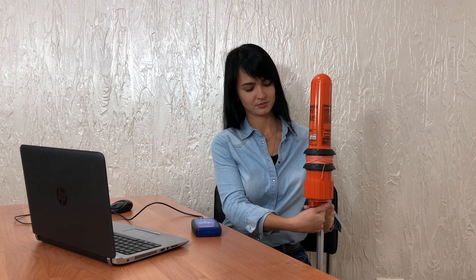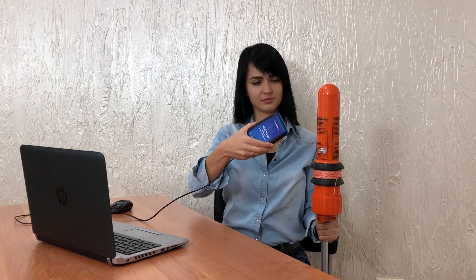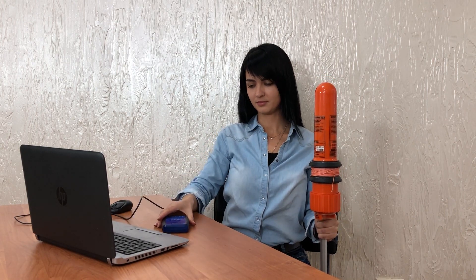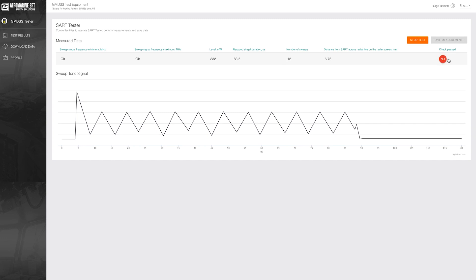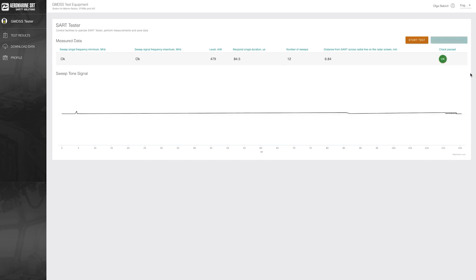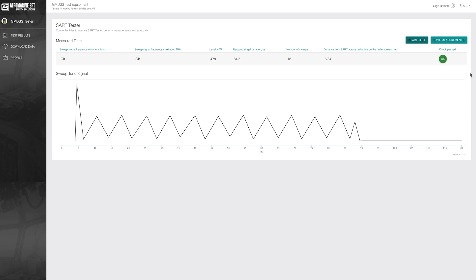Turn on the SART and the measurements begin. We hear audio confirmation of signal presence. We see the sweep tone signal in a saw-like graphic with 12 sweeps. The check pass status now shows OK, so the SART has passed the test. Here are the minimum and maximum frequencies checked, level of signal in mW, response signal duration, and number of sweeps — they are 12, and here they are on the graphic.